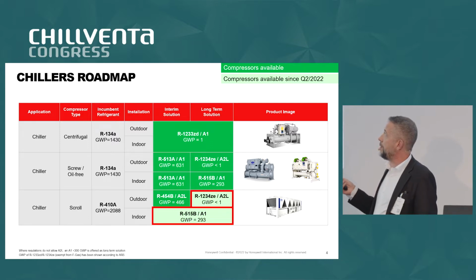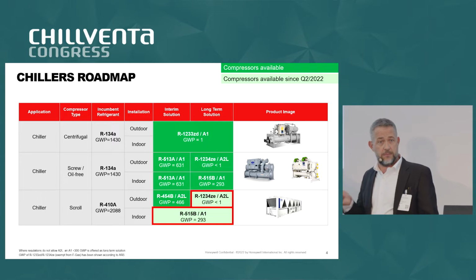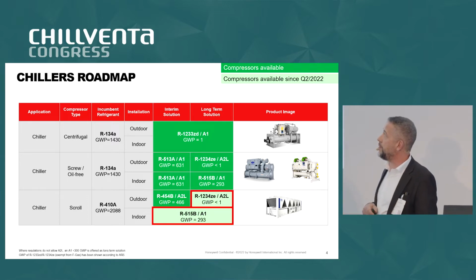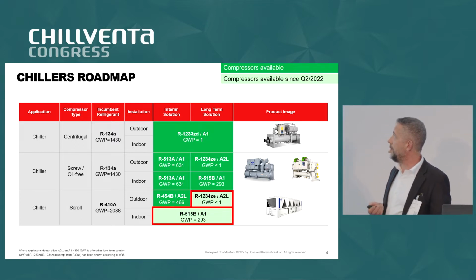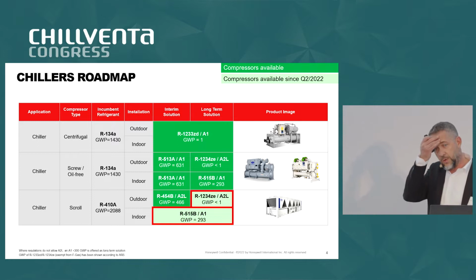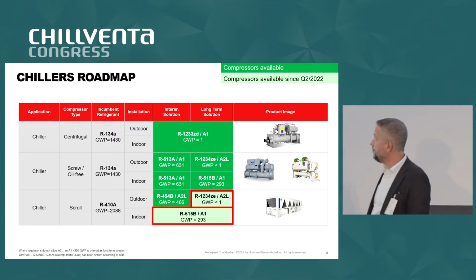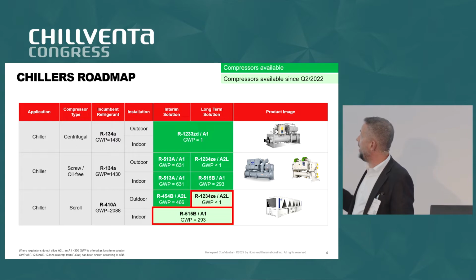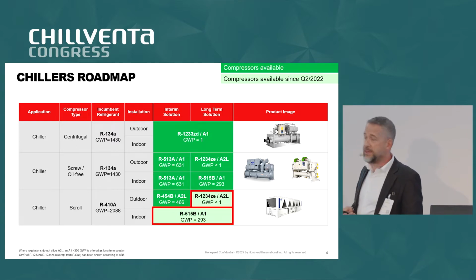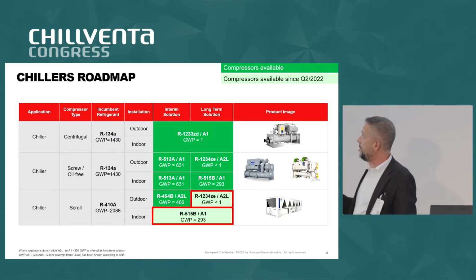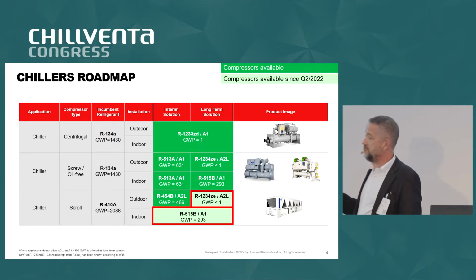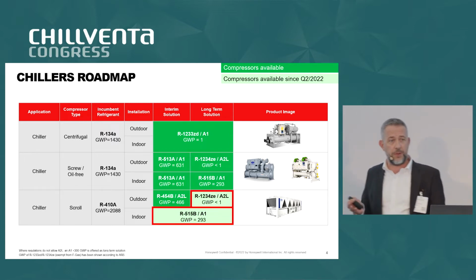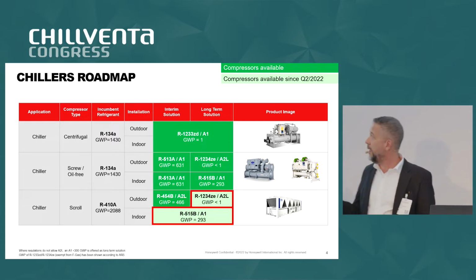For some options, the long term is already in place, like the large centrifugal chillers, where they transition from R-134a to R-1233zd, a pure HFO, GWP equals 1 and A1, non-flammable. Then the screw and oil-free centrifugal compressors transition to R-1234ze and R-515B, which is, I would say, a copycat, a very similar product. You cannot make a difference when testing.